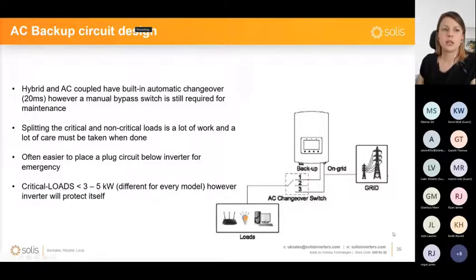I was mentioning a little bit earlier about the backup circuit design and the need for having an AC changeover switch. Even if the inverter inside has its own automatic changeover in order to switch the power supply for the critical loads from being supplied from the grid to being supplied from the battery, additionally, you're going to need this changeover switch in order to be able to supply these critical loads even if the inverter is out of service or requires maintenance.